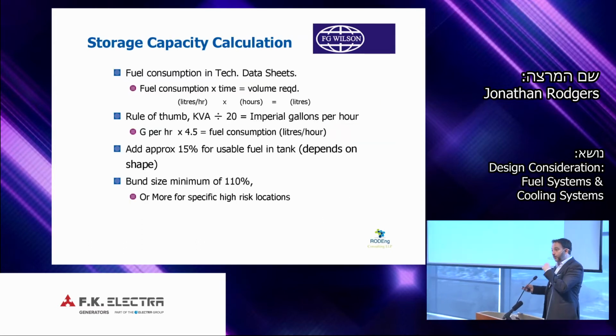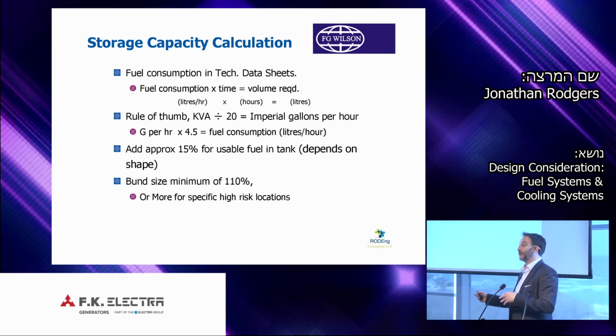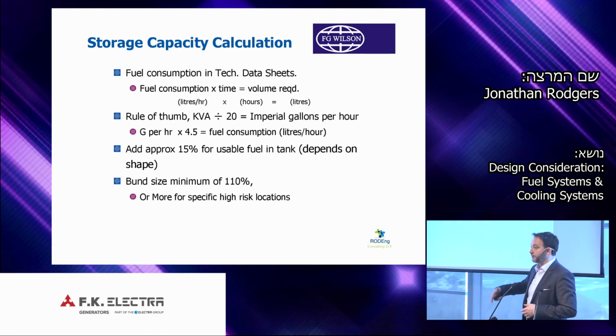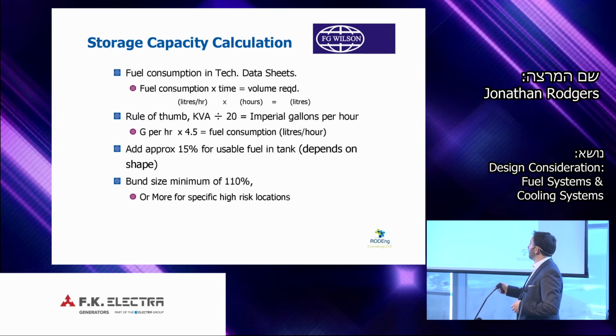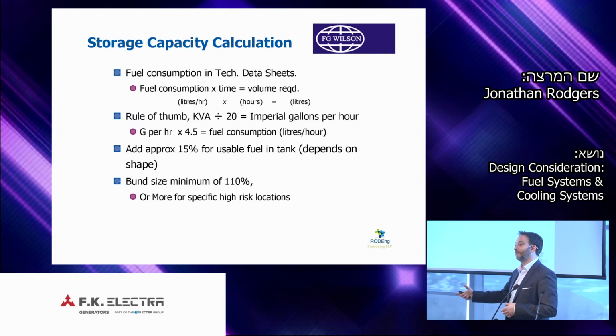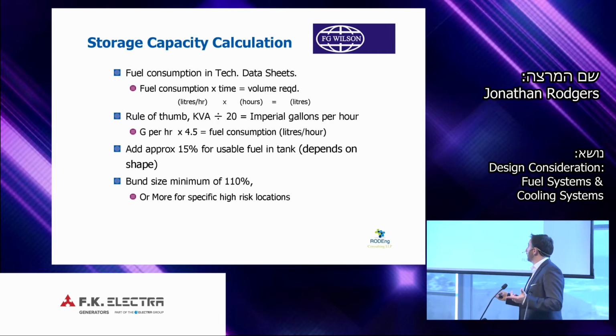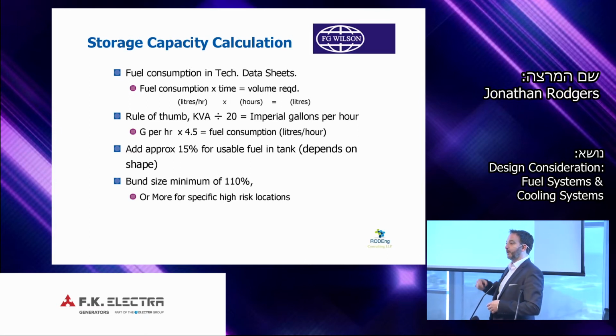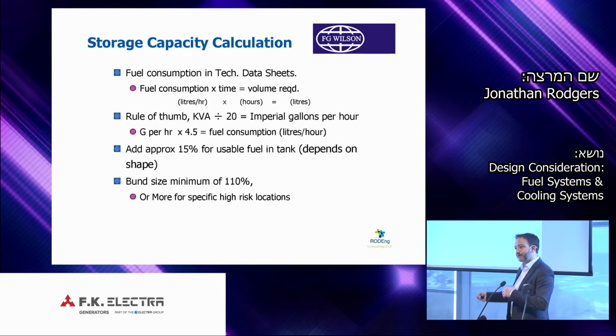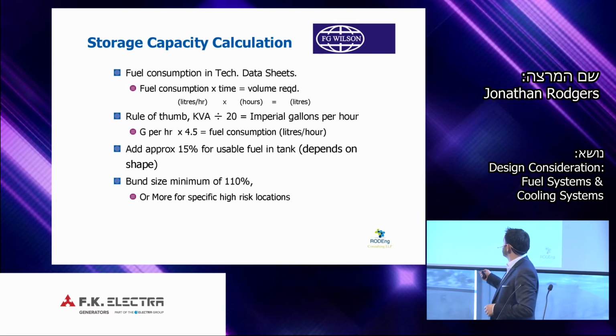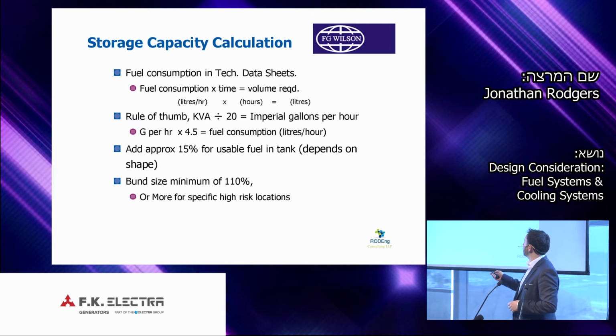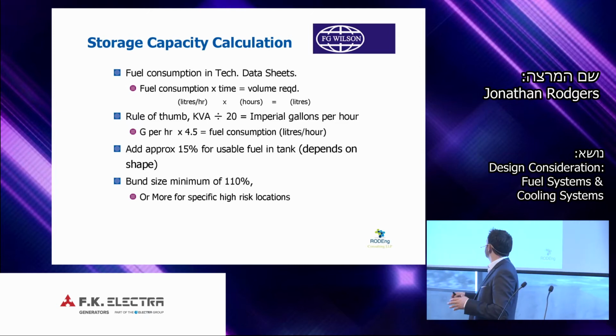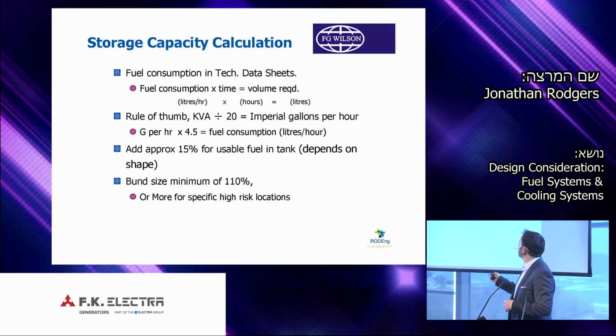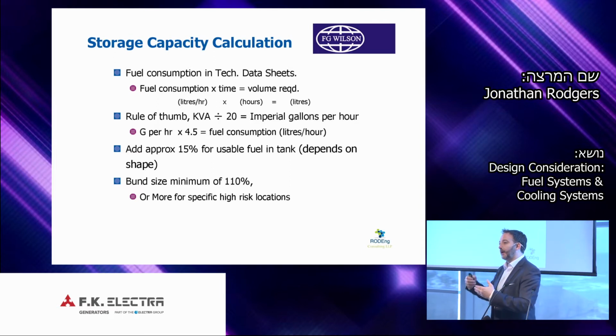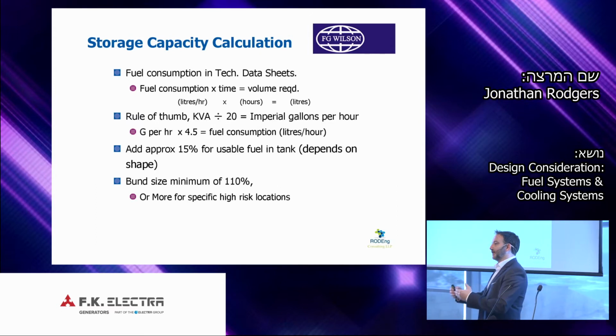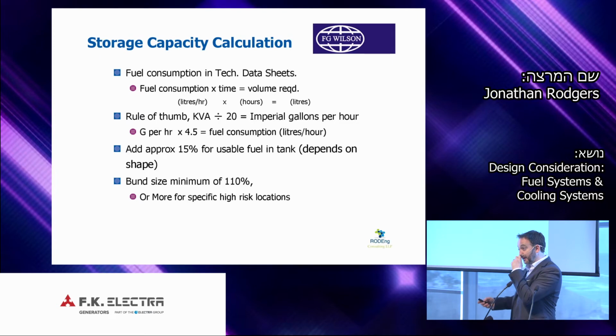So firstly, with storage, we need to know how much fuel we need to store. Basically, it's simply taking the fuel consumption of the engine, taken from a data sheet, multiplying it by the number of hours that we want to have running, and this gives us our total volume in litres. If it's a design, we may want to use a rule of thumb. There's also a rule of thumb in gallons instead of litres, depending on the territory. Basically, we take the kVA, divide by 20, and this will give us the number of imperial gallons, not US, but imperial gallons per hour. Another approximation. So these are rules of thumb, if you haven't finalized the generator selection, if you haven't made the exact selection of engine at a specific rating yet, and you're looking at an approximate kVA rating.